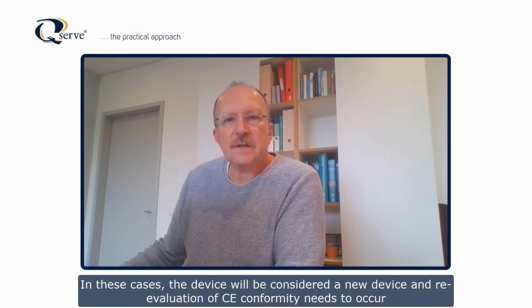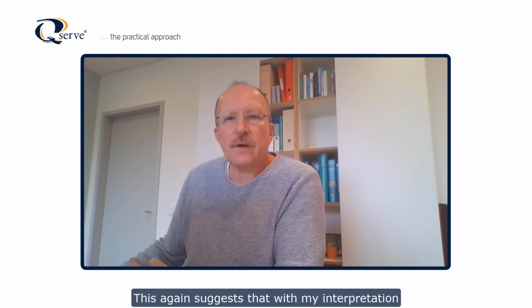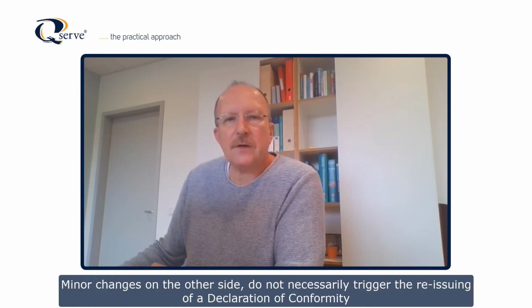In these cases, the device will be considered a new device and a re-evaluation of CE conformity needs to occur. This again suggests, according to my interpretation, that minor changes on the other side do not necessarily trigger the reissuing of a declaration of conformity.